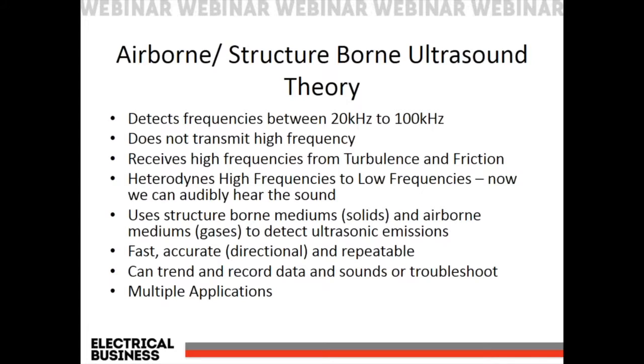Our instruments heterodyne these high frequency sounds, and heterodyne is just a very fancy word for saying that it translates these high frequencies down to an audible range, so now we can hear them. Otherwise, we can't hear high frequency ranges because they're above our hearing level. So the heterodyning happens in the instruments, which allows us to audibly pick up these sounds in our headphones while it's being translated down to a range that we can hear. We use structure-borne mediums and solids, like a motor, maybe a gearbox, to hear through pipes, valves, etc. We also use airborne mediums like gases to detect ultrasonic emissions, and again that comes from turbulent flow and/or friction.